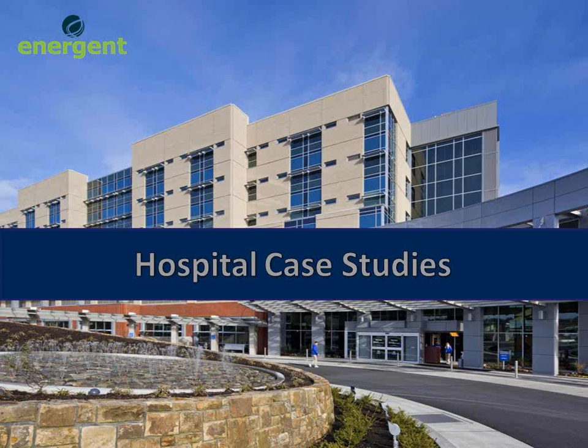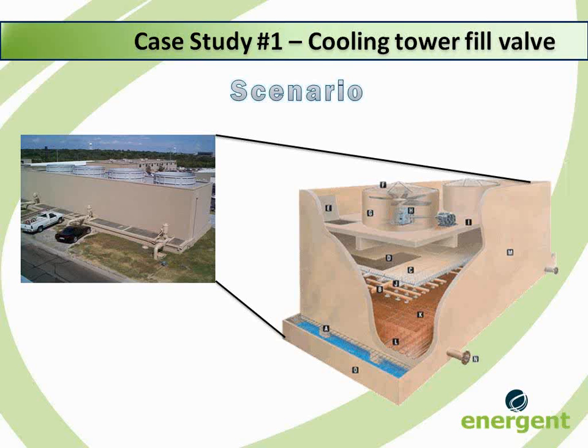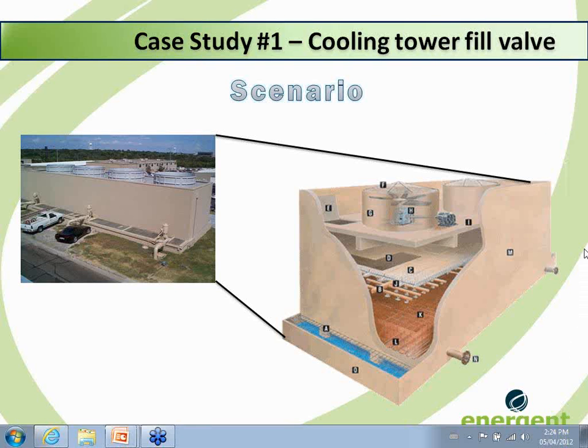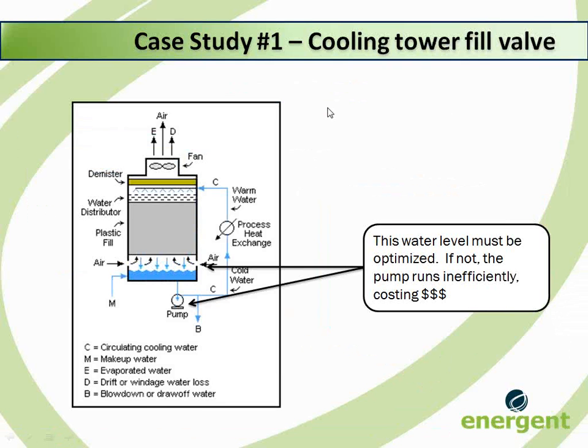These 2 case studies are for hospitals that are in the Ontario area. Scenario 1. Our first case study focuses on a unique scenario. The hospital client uses cooling towers to manage their cooling needs, very similar to the one pictured here. Energent software platform and their energy analysts were able to detect a situation in which a cooling tower wasn't operating at maximum efficiency and were able to measure the exact impact of that situation.